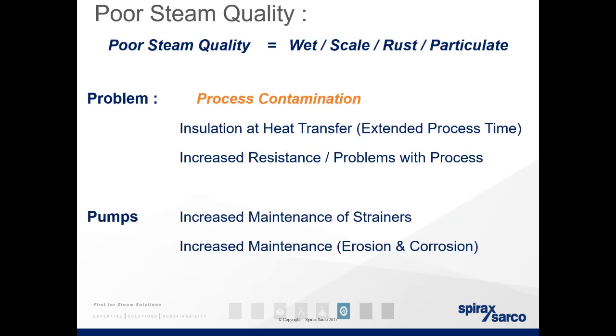Poor steam quality equals wet steam, scale, rust, particulates in your system. Problems can be process contamination, insulation at heat transfer, extended process times. The wetter your steam, the less enthalpy it will carry, the less heat or energy it will transfer into your product or your process. And increased resistance, so problems in process, problems with getting steam down the lines, problems with overcooking or undercooking. Pumps, increased maintenance costs because of strainers, and increased maintenance from erosion and corrosion.